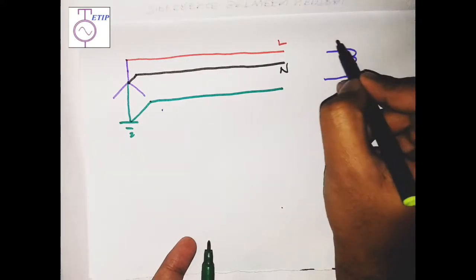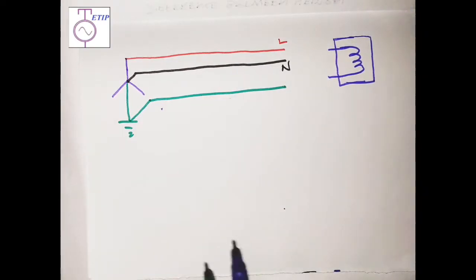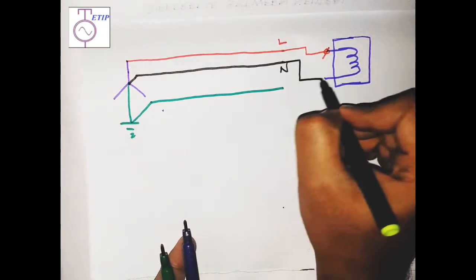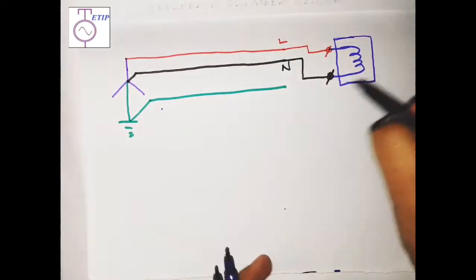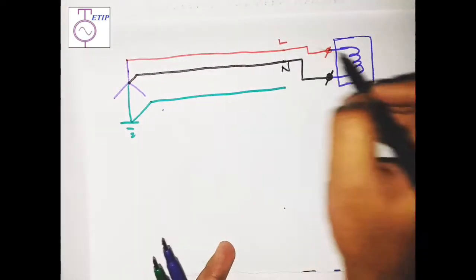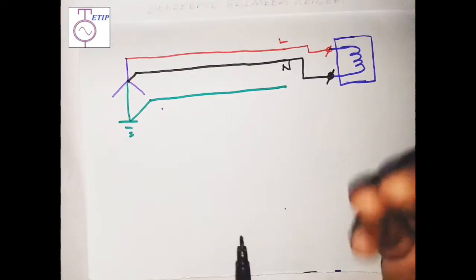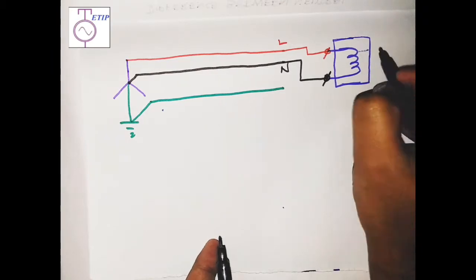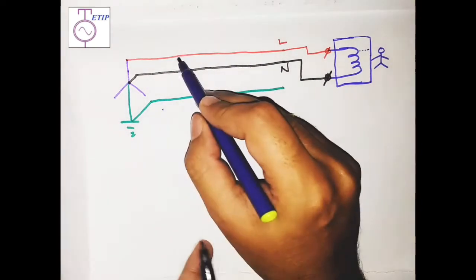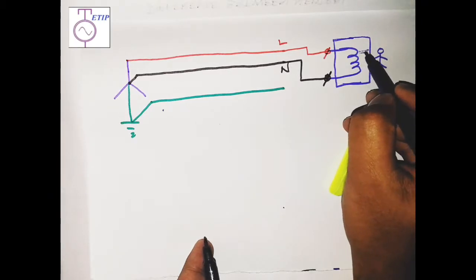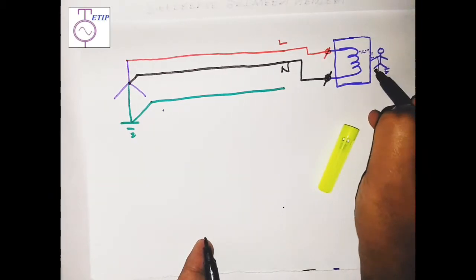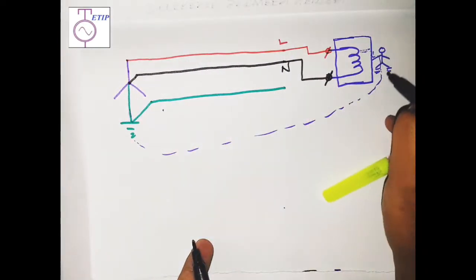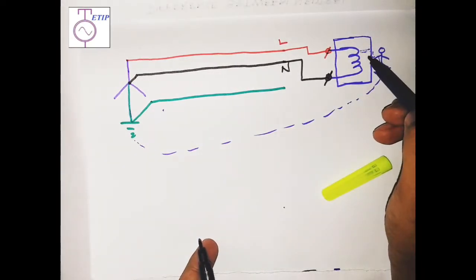Suppose this is my load and this is its enclosure. If I connect line to one end and neutral to the other end, the load will operate and current will flow. However, there is an accidental possibility: if the insulation between the winding and the enclosure damages, or a conductor breaks and touches the enclosure, and a person touches it, current will flow through the line conductor, through the broken insulation, through the person's body to earth — causing a huge shock.